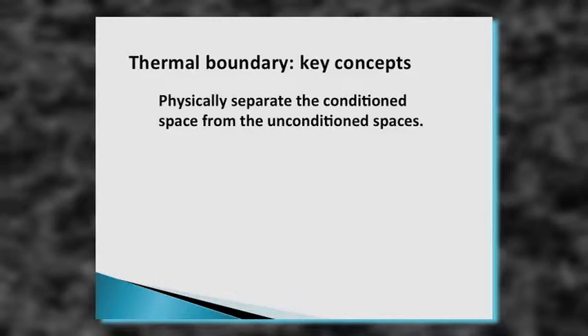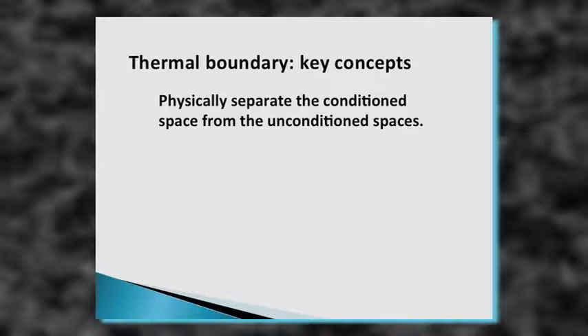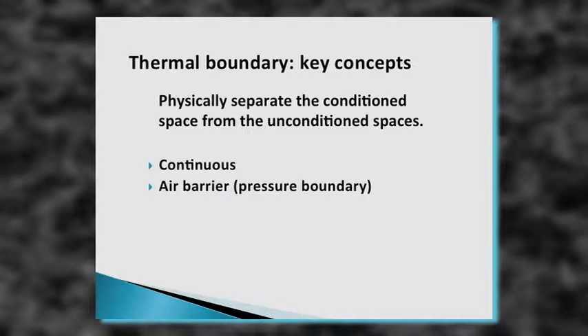Here are some key concepts about the thermal barrier. The thermal envelope is made up of the thermal barrier and the air barrier. What do they need to be? They have to be aligned with each other and they have to be continuous — continuous and aligned. For the thermal barrier to be effective, it has to be continuous, have an air barrier right next to it, and have a vapor barrier, because we can't allow our thermal barrier to get wet.